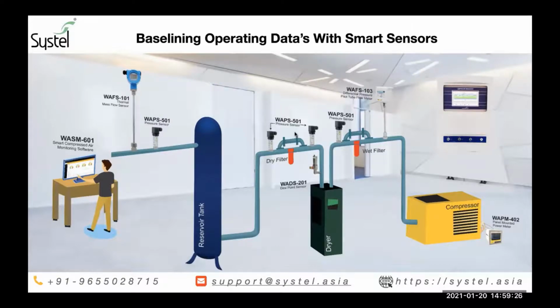Once this moisture enters your system, there are a lot of tangible effects. It creates rusting and scaling in your pipelines, it creates pressure drop, and it also damages the seals of your pneumatic components like actuators, valves and connectors. These are the major root causes of recurring leaks in your system. So maintaining the pressure dew point at a very low level will ensure that the maintenance of the downstream of the system is considerably lower.